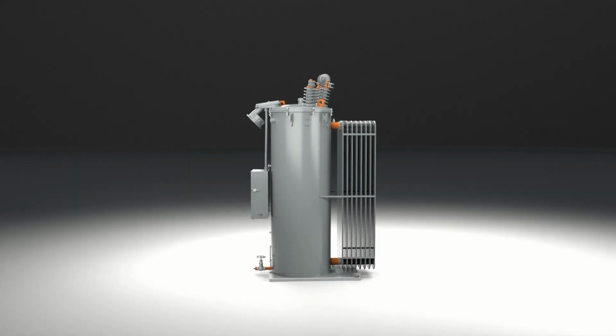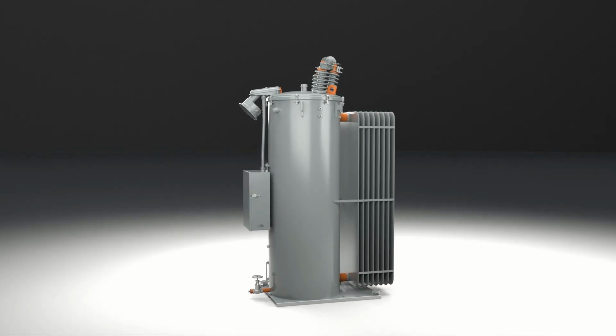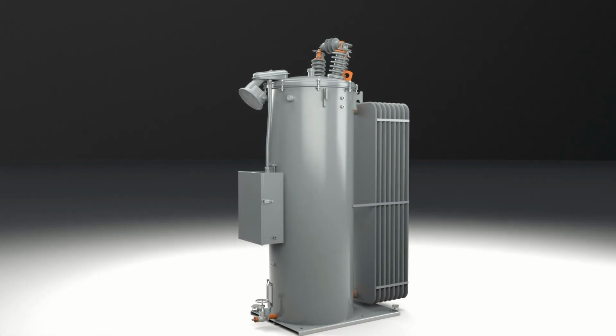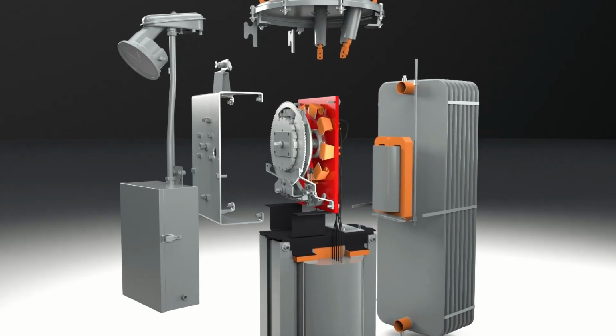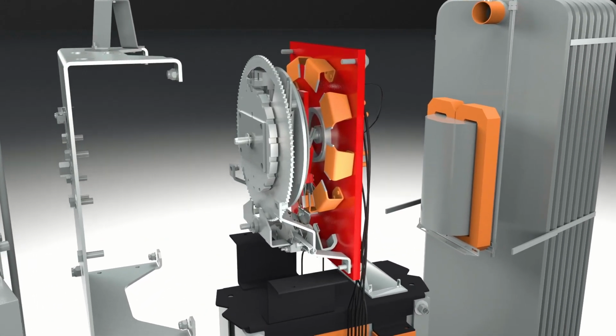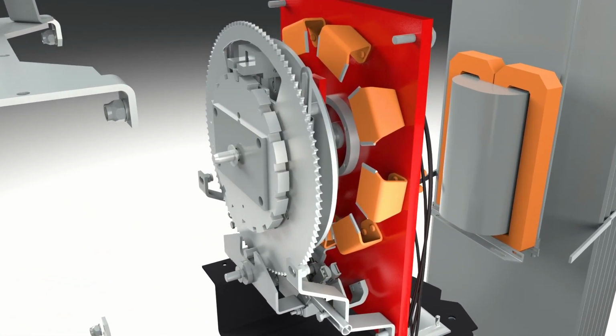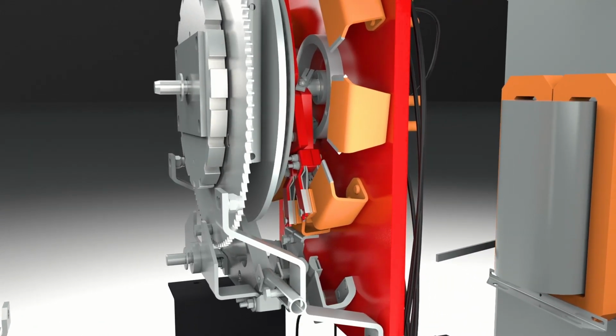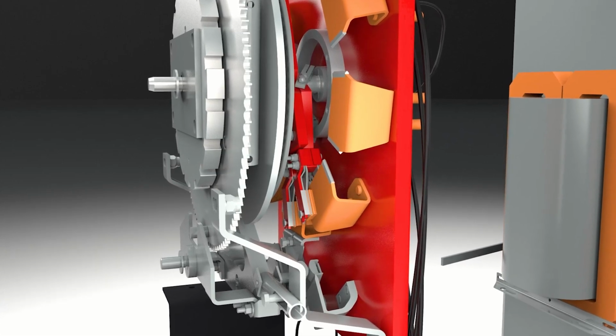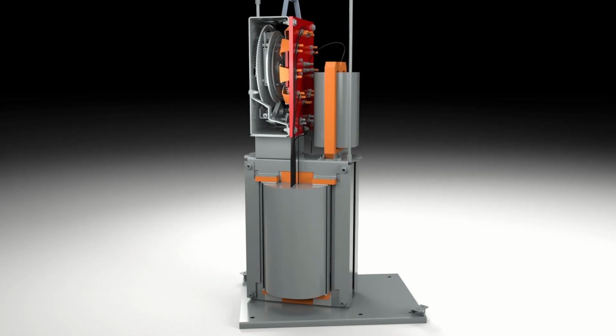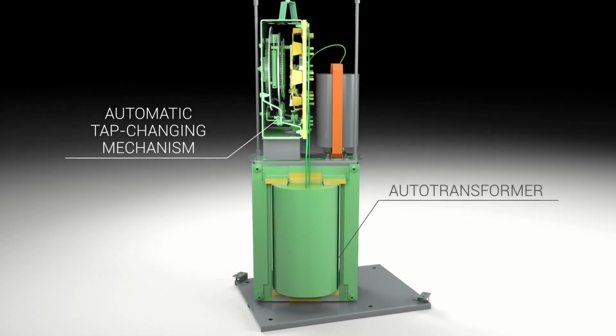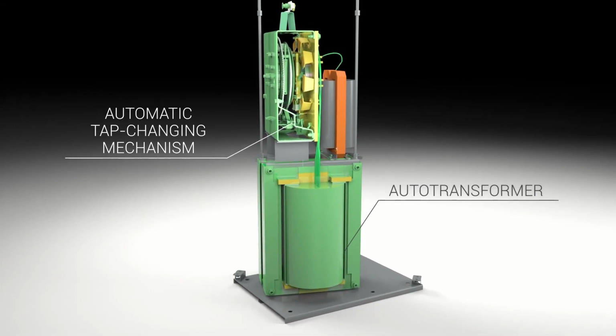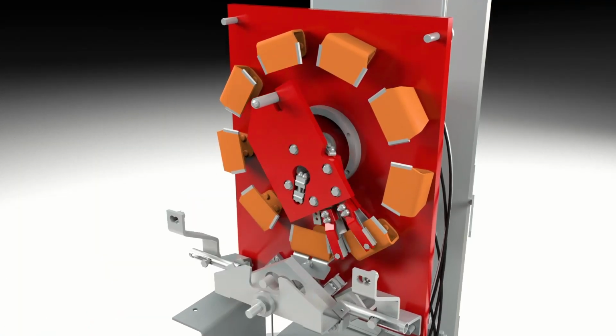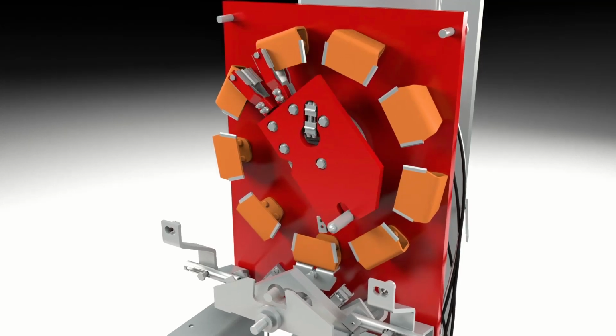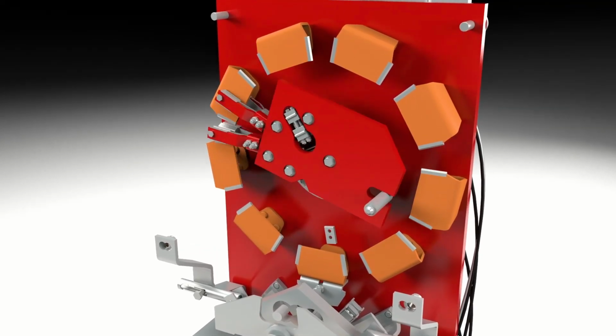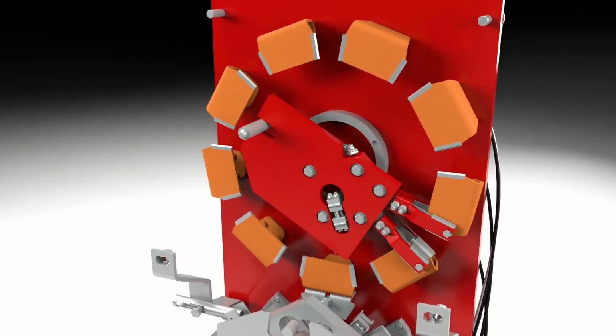Inside a substation, voltage regulators automatically step the voltage of a line up and down as the amount of electric demand changes. Regulators are key to correcting the supply of voltage to each line and to minimize voltage swings between light and heavy load periods. When electric demand increases, a regulator will automatically step up to supply more voltage so that the electric equipment runs properly. A regulator has an auto transformer and an automatic tap changing mechanism that changes voltage in equal steps. There are 16 raised positions on the regulator that increase voltage, and 16 lower positions that step down voltage based on electric demand.